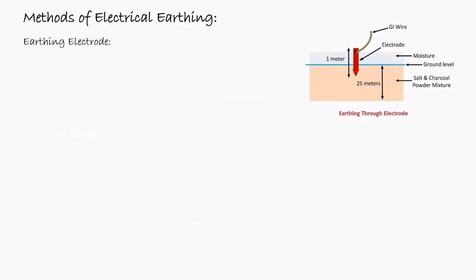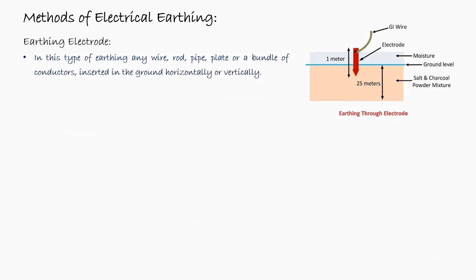Next is the earthing electrode. Here in this figure we can see the earthing electrode is used, which is put in the ground. In this type of earthing, any rod, pipe, plate or bundle of conductor inserted into the ground horizontally or vertically is considered an earthing electrode.